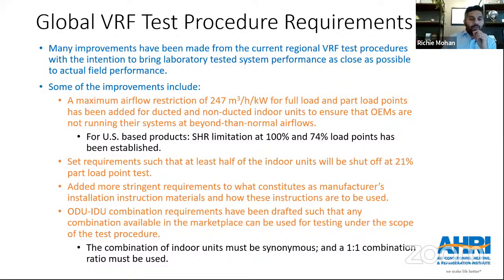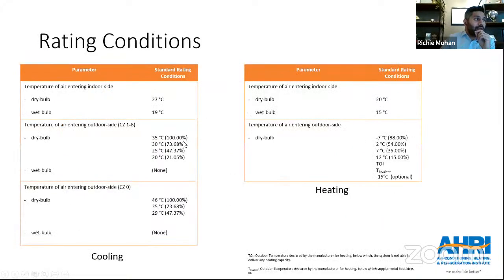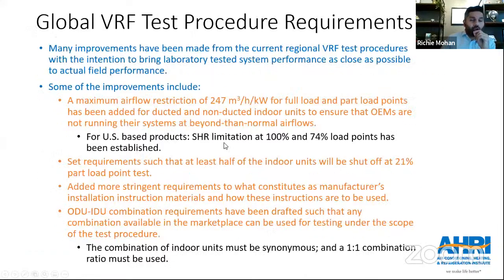As I mentioned in one of my previous slides, there might be deviations based on different regional requirements. This is the first example of that: for US and Canadian-based products, there's going to be an SHR, or sensible heat ratio, limitation added for the full load point, which is the 100% load point for cooling, as well as one of the part load points, the 74% load point for cooling. Let me go back and show you the rating condition—these are the two particular points where we've added an SHR limitation for cooling.